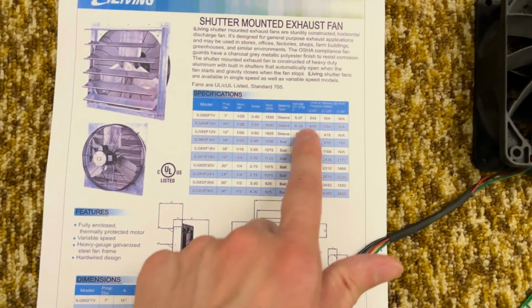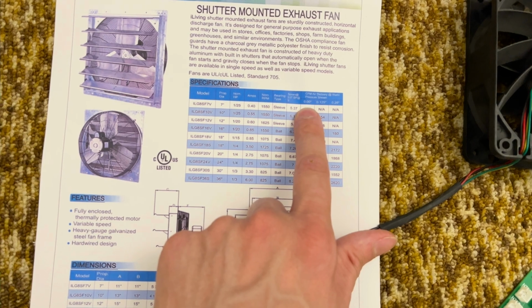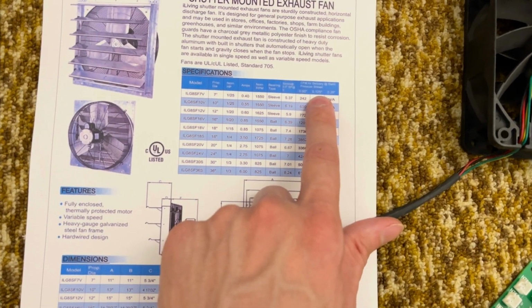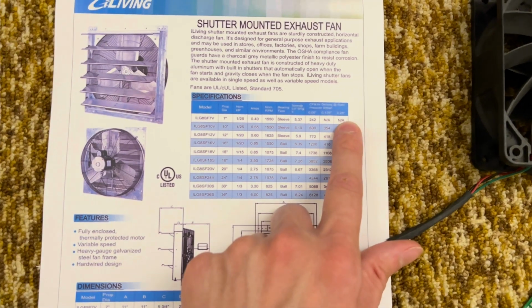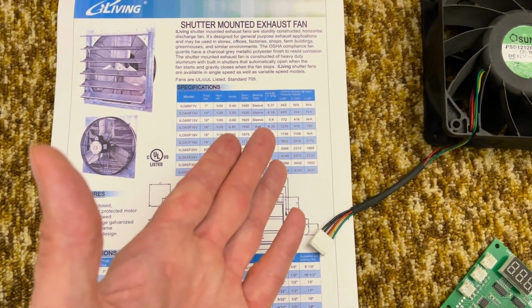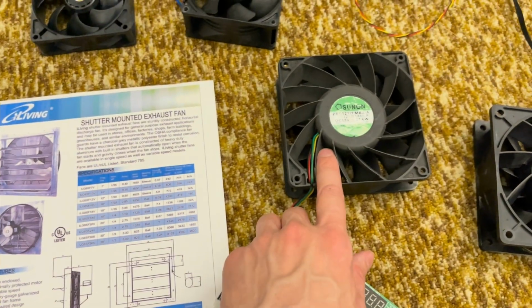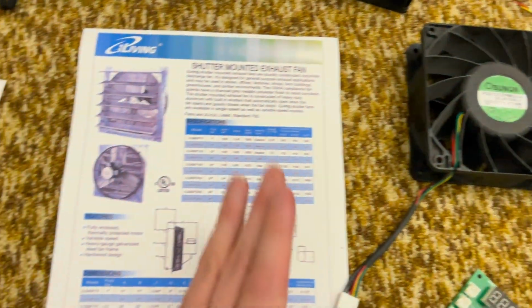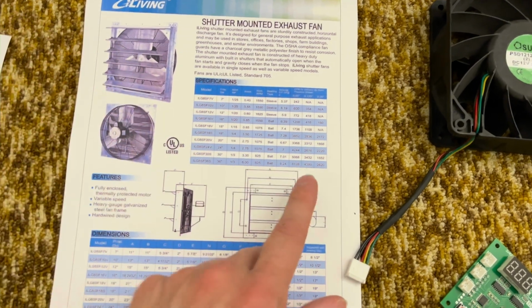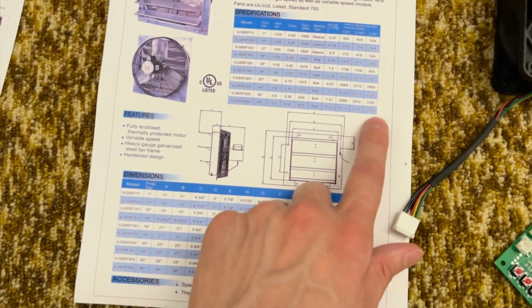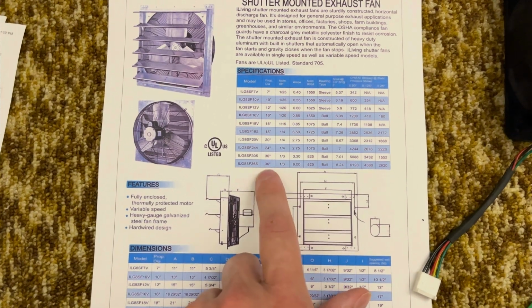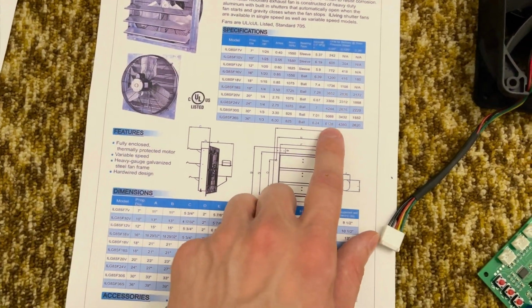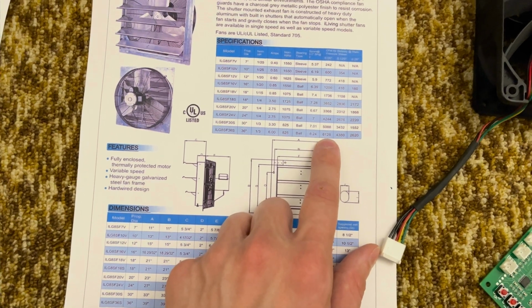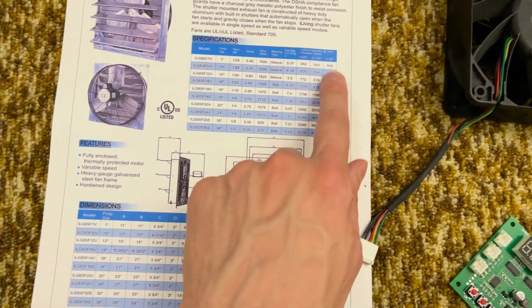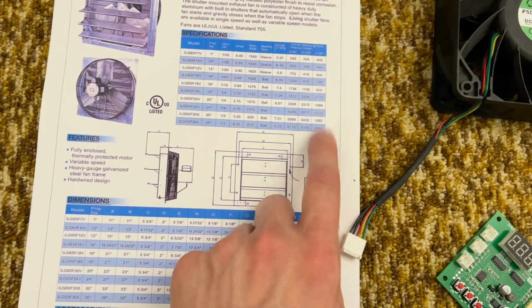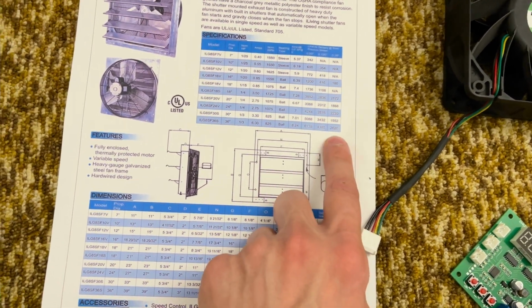Like you can see here, this is airflow into zero static pressure, an eighth inch water column, and a quarter inch water column. That's one of the units that are used for static pressure. These might be in pascals or bar. They've used several different units, but they're all convertible from one another. And this guy, the largest model, the 36 inch version of this fan, with no static, will move 6,100 CFM. However, with a quarter inch of static pressure, 2,600. So that's less than half the airflow.